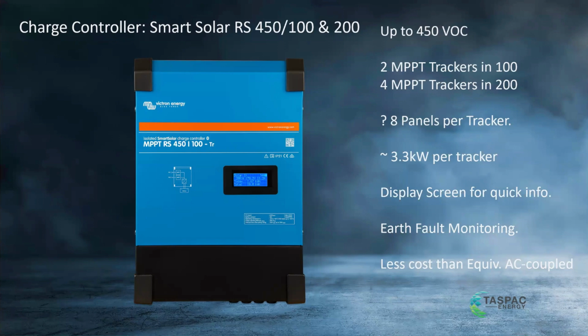considerations of an off-grid or a hybrid grid connected ESS system. It is a game changer because what it means is you no longer have to run a cable from the solar array for every 3 panels. You can now put, say, up to 8 panels, sometimes 9, depending on the voltage of the panels. You can put 8 in series, run that down through an isolator straight into the inverter, the charge controller. And the 100 amp charge controller has 2 separate MPPT trackers. The 200 amp charge controller has 4.